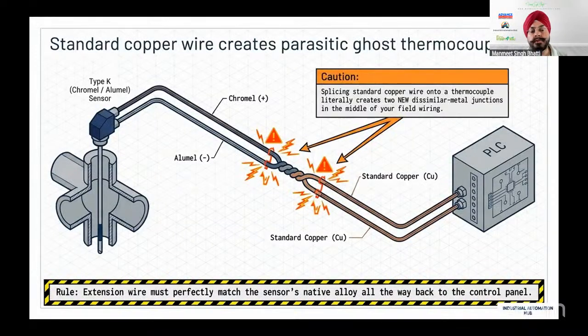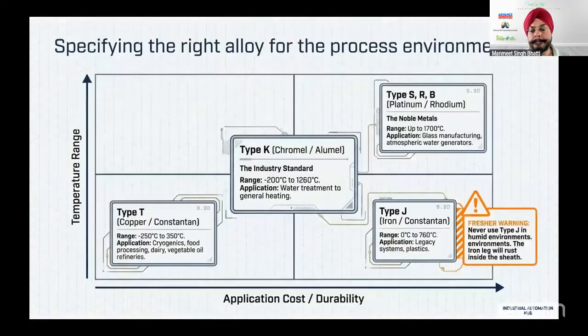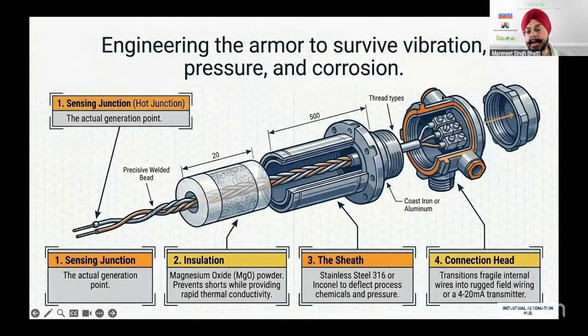Second way, and the best way, is to always put a transmitter on top. If you see on the head, on the right side, there are 3 wires, the connection head. As soon as the wires of the thermocouple are connected to this head, on the head we install a transmitter. What the transmitter does is convert your thermocouple input directly into 4 to 20 milliamp. So instead of a thermocouple or millivolt output, we are directly getting a straight 4 to 20 milliampere output.